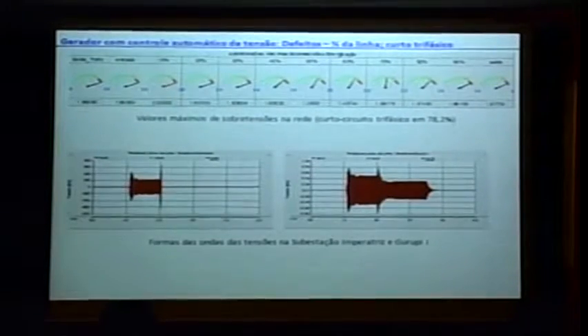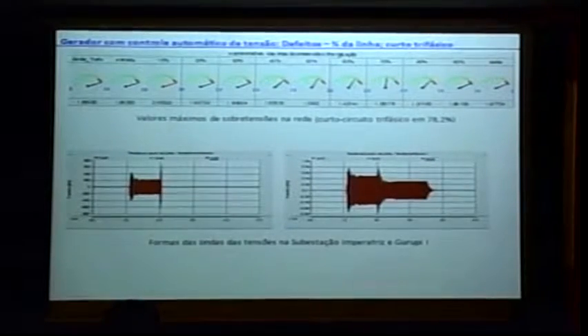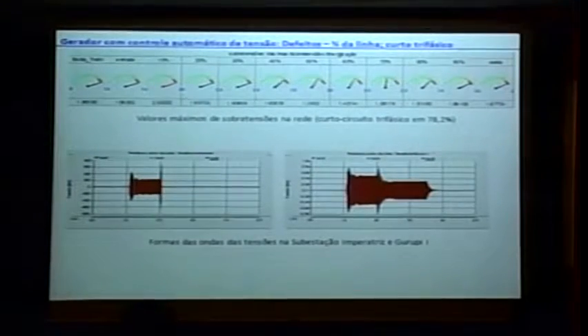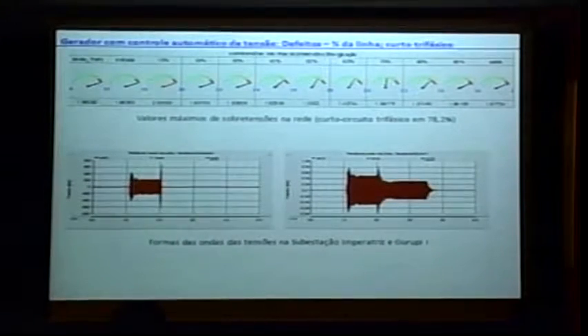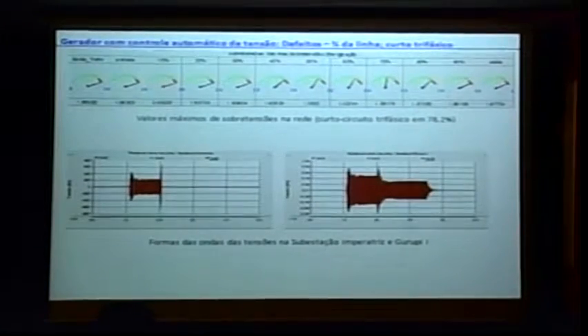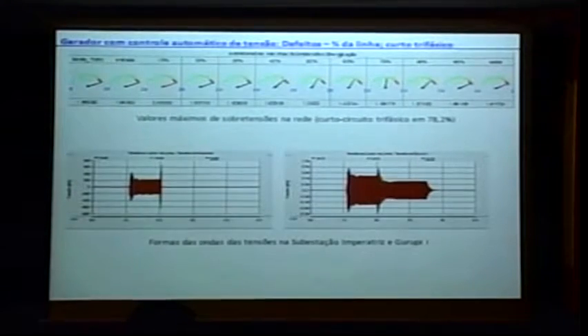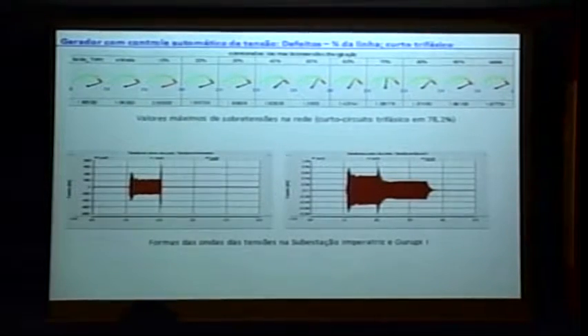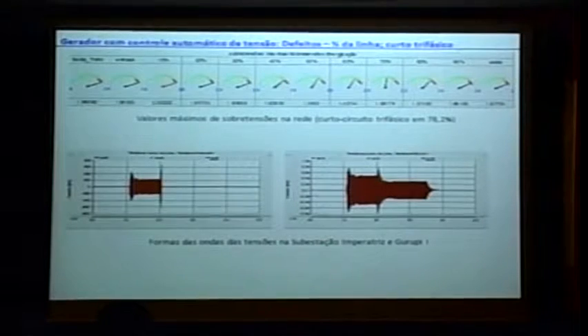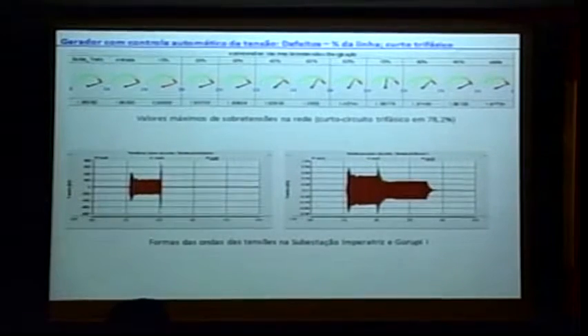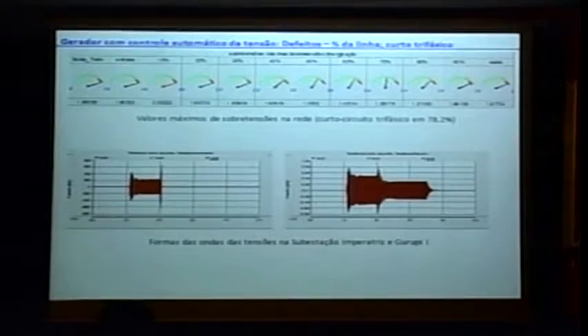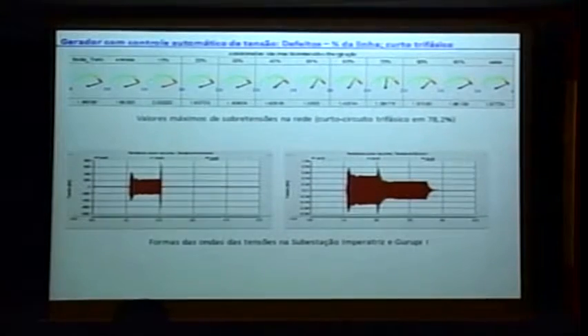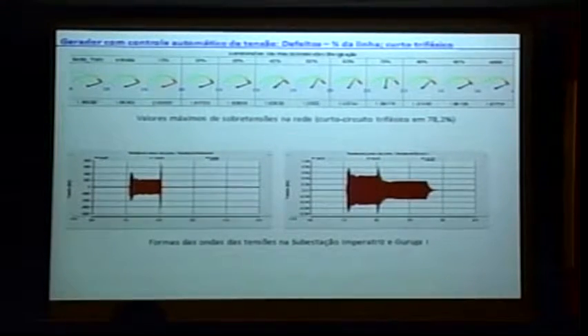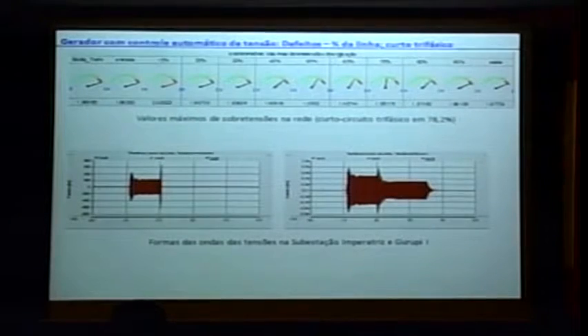We had the over tension or over voltage of 1.2 pu in the beginning, and then in the middle line we had the valley of voltage. But during the fault, you're going to have over tension, over voltage here in the middle line. Here's the maximum value of the over voltage during short circuit, below 2 pu. And the behavior in this case of the line was different. That was the actuation of the Imperatriz gap.